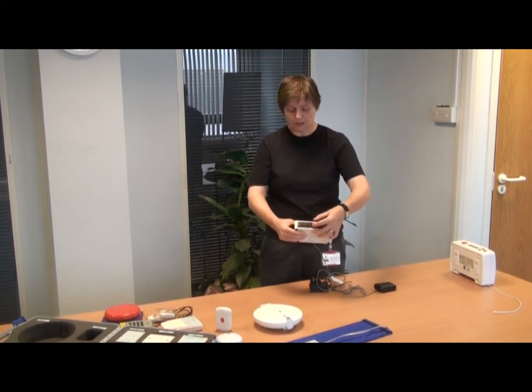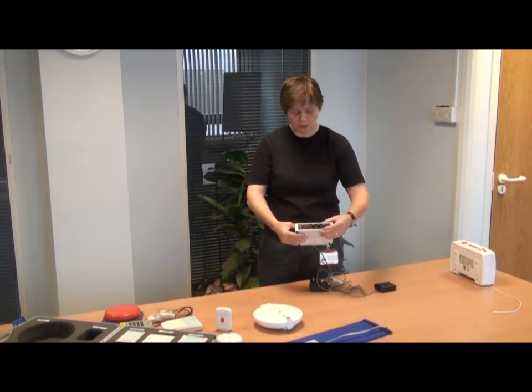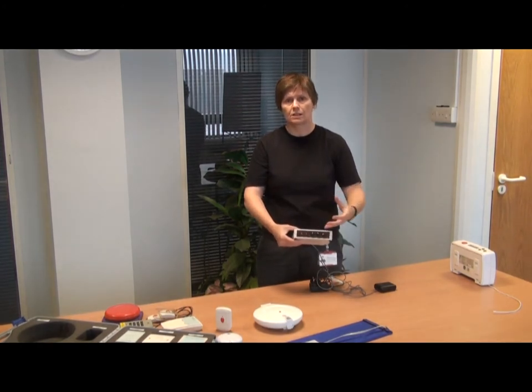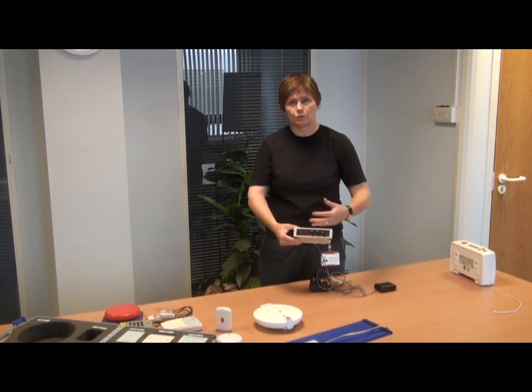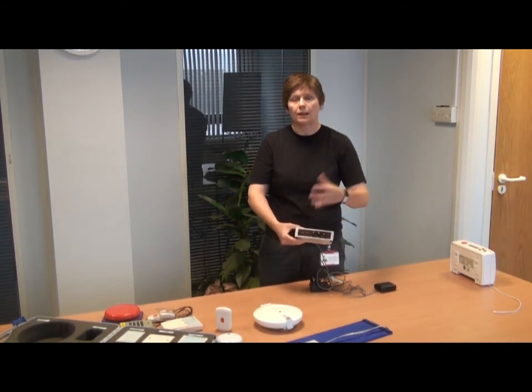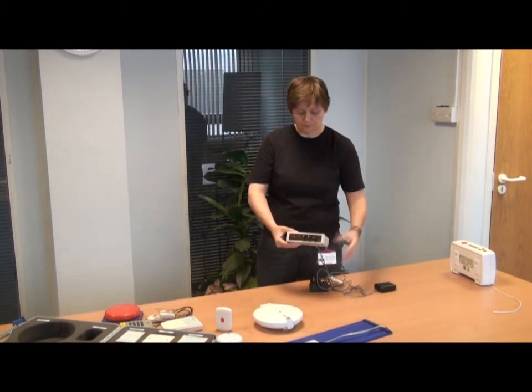The sensitivity can be adjusted. It has a microphone, because some people's seizures make an audible sound. It also has a delay function in case the seizure is self-limiting, in which case you can let the individual sleep through the seizure. But if it goes on for longer than a minute or two, then the device would activate.